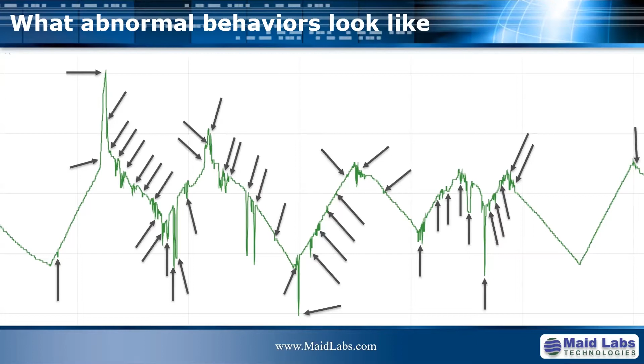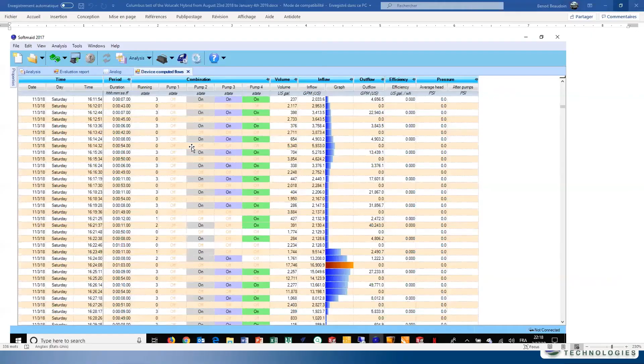At some point you can see the level was getting very high, so all 3 pumps were starting and stopping repeatedly. In reality it looked like this: all 3 pumps starting at the same time, running for 7 seconds before stopping for 45 seconds, then restarting for 6 seconds, stopping for 42 seconds, and this went on for hours.